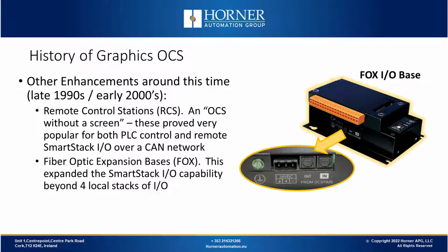We also introduced fiber optic bases, or FOX bases. These allowed SmartStack I/O to be stacked on these remote bases that were connected using fiber optics up to 10 meters away from the OCS. That gave the potential of having a total of 20 modules between what's stacked on the back and the remote I/O bases. So with some of these graphical OCS systems, the I/O count can be a bit larger, which we have to consider when we're doing our retrofits.